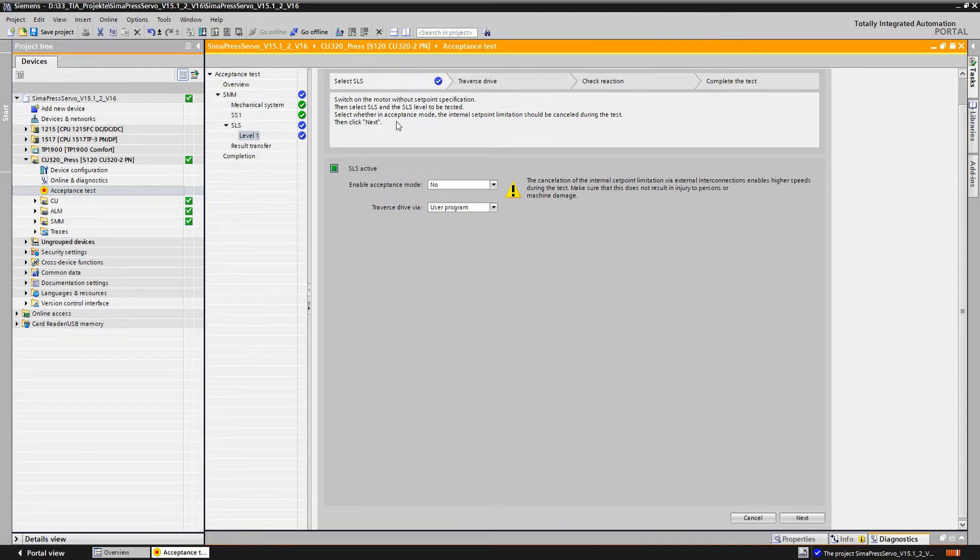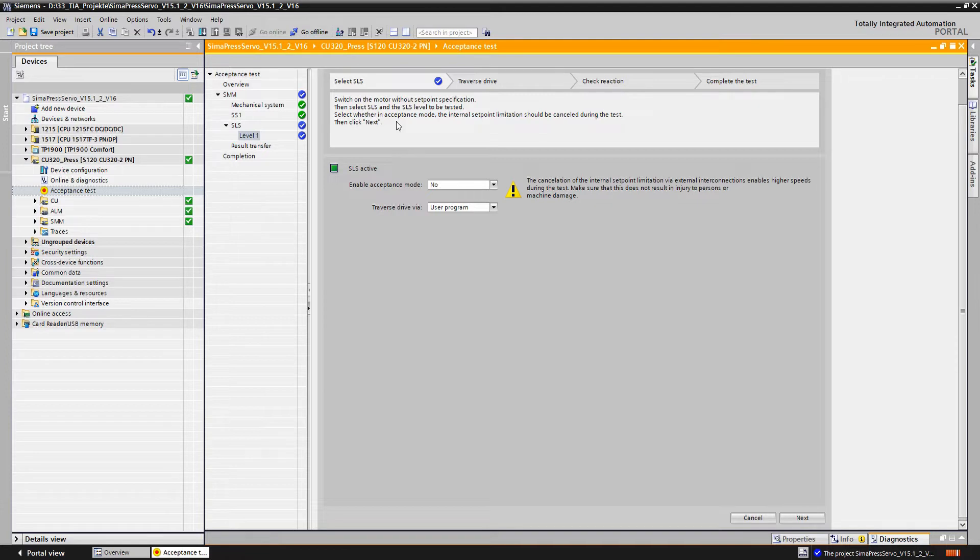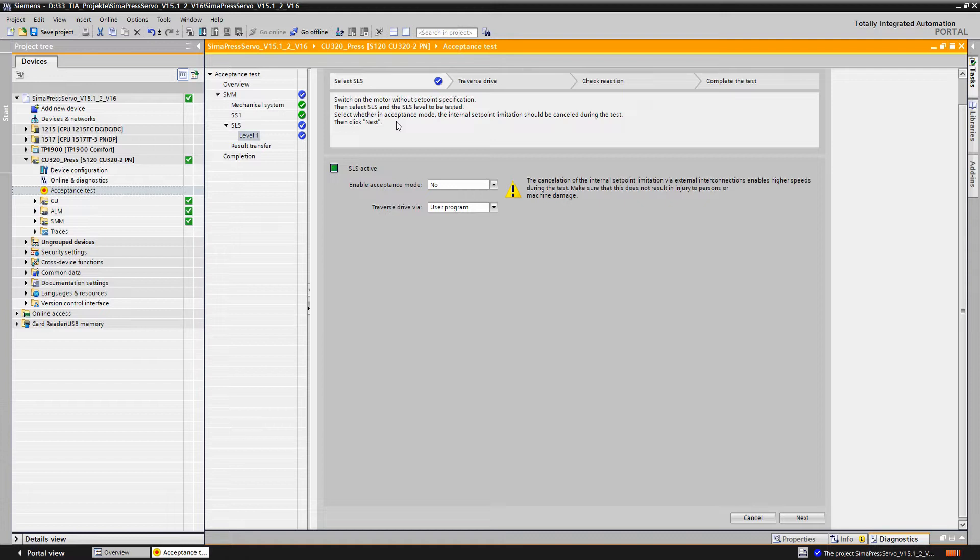In our example on the machine, this is already done by switching over to the setup mode. To check whether the SLS limit has been parameterized correctly, it must be possible to exceed the SLS limit value. This must either be done in the user program or alternatively via the drive control panel.